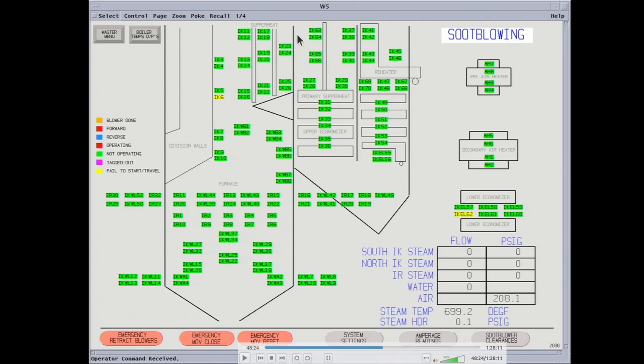Comes out through primary superheat and upper economizer — the back box has two separate sections. You've got the reheater on the back and the primary superheat and upper economizer, then lower economizer on the outlet. Dampers maintain the flow and change the flow between these two sections to maintain reheat temperature. Soot blowing is critical — these things can plug really quickly depending on the kind of coal you're burning, and even the amount of excess air can be a major factor. Soot blowing runs pretty much continuously and takes around 30,000 gallons per hour of water to run all the soot blowing.